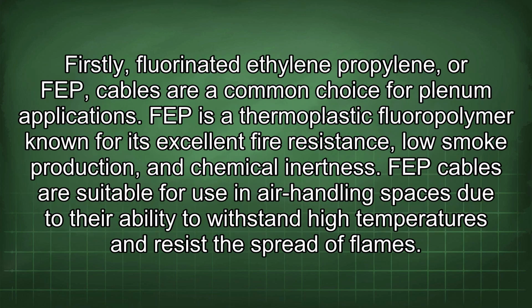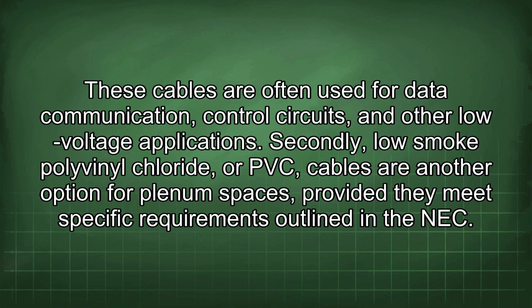Firstly, fluorinated ethylene propylene, or FEP cables, are a common choice for plenum applications. FEP is a thermoplastic fluoropolymer known for its excellent fire resistance, low smoke production, and chemical inertness. FEP cables are suitable for use in air handling spaces due to their ability to withstand high temperatures and resist the spread of flames. These cables are often used for data communication, control circuits, and other low-voltage applications.